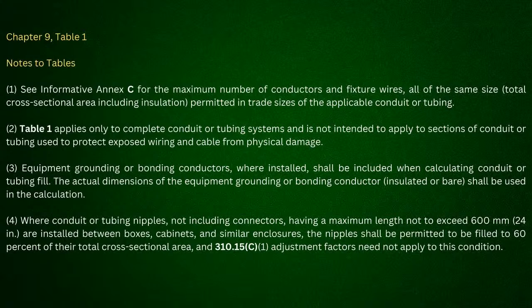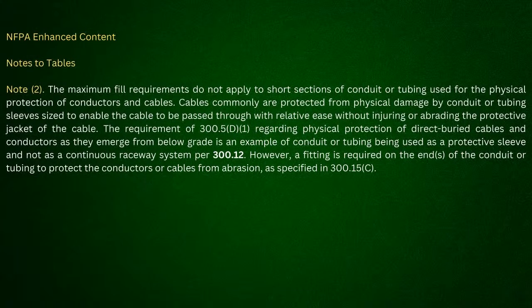Okay, well, just hold on. I will go over and we will read and see who's got it. Okay? So this was from NFPA Enhanced Content. It says the maximum fill requirements do not apply to short sections of conduit or tubing used for physical protection of conductors and cables. Okay? Then it says cables commonly are protected from physical damage by conduit or tubing sleeves. They literally tell you it's a sleeve. sized to enable the cable to be passed through with relative ease without injuring or abrading the protective jacket of the cable.